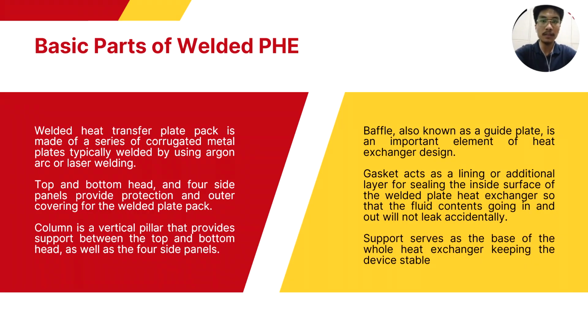Basic parts of welded PHE. First one, the welded heat transfer plate pack, is made of a series of corrugated metal plates typically welded by using argon arc or laser welding. This is where the fluids, hot and cold, flow, and also where the heat transfer or heat exchange occurs.